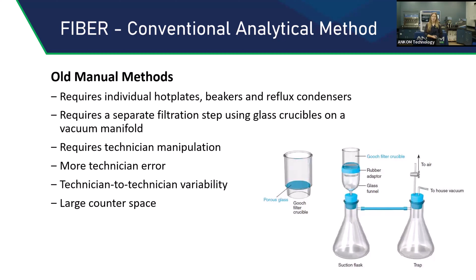We have our ANKOM DELTA fiber analyzer that analyzes up to 24 samples at a time, which is about 96 per day. I believe over 100 for crude and detergent fiber per day. This instrument incorporates an internal pump system that draws chemicals from any source within 10 feet of the instrument. So you can see in this picture, your cubetainers are underneath the counter, and you have tubes that are plumbed to each of your reservoirs.